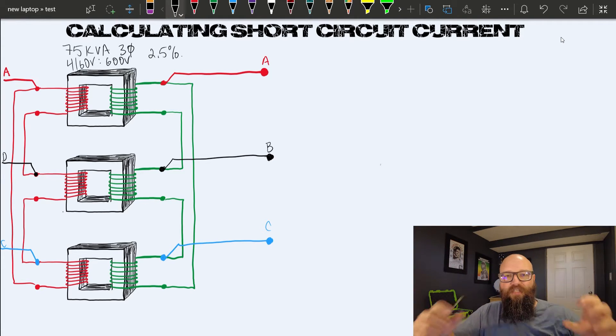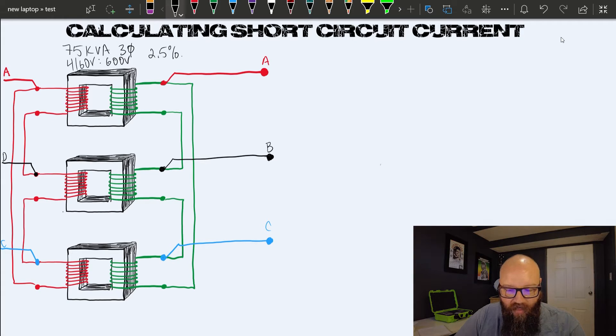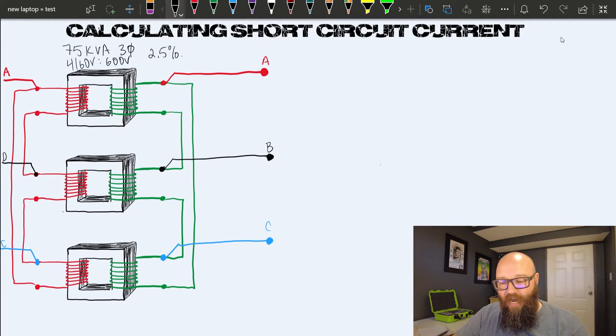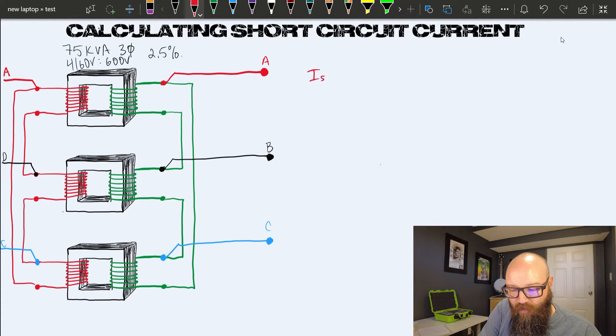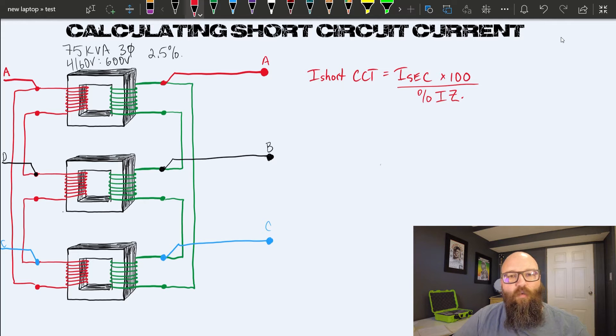Imagine this is one box with three single-phase transformers inside. We have our ABC terminals here. We're not going to focus too much on the transformer theory, but we want to calculate the short circuit current available from this system. We're going to look at our same formula: I short circuit equals I secondary times 100 divided by percent IZ. In this case, we need to know the I line secondary, and it's simple to determine using the same formula we used before.